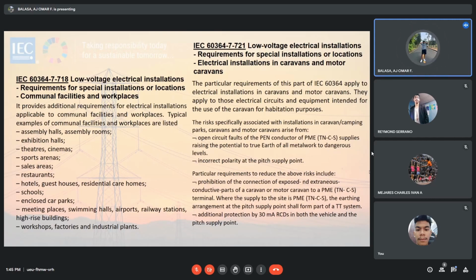Risks specifically associated with installations in caravan camping parks, caravans and motor caravans arise from open circuit faults of the conductor of PME TN-C-S supplies, raising the potential to earth of all metalwork to dangerous levels, and incorrect polarity at the pitch supply points.